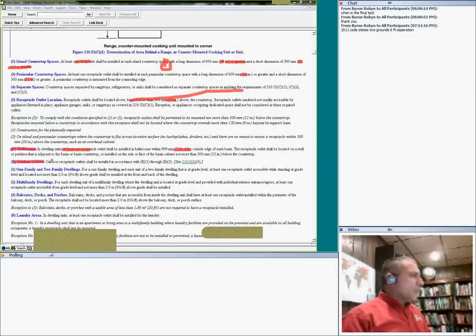Outdoor outlets: you need outdoor outlets, and the inside shall be installed in accordance with E1 and E3. On a 1 family and 2 family dwelling, you need 2 receptacles, 1 in the front and 1 in the back, above grade, and they should not be more than 6 feet 6 inches.